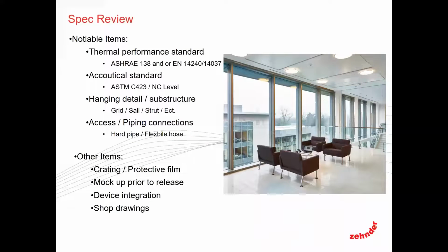So, all right, quick spec review, things that I want everybody to walk out of here making note of. When you write your specs and look at jobs, make sure you're writing down the standards, the thermal performance, whether it's ASHRAE 138 or the EN standards, depending on if it's heating or cooling. Make sure you're working with the architect to specify the acoustical standard in the space, and that you're lockstep on both sides of that. Substructure, whether it's going into your lay-in grid with the hanger kits, or if you're talking more complexity and going into the metal ceiling, integrating with the architectural side, make sure you're coordinating with the architect so you're both on the same page. And then access and piping, make sure you're noting what's being used to connect those.